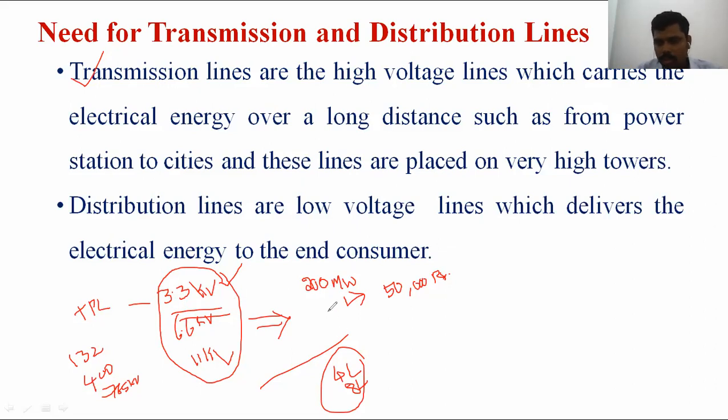But here the cost is how much? Here we are spending 4 lakh to 8 lakh. But here, with the help of the step-up transformer, the cost comes to only around 50,000. Additionally, we are adding only one transformer for that purpose. And why are we boosting the voltage? We need to minimize the I square R losses.